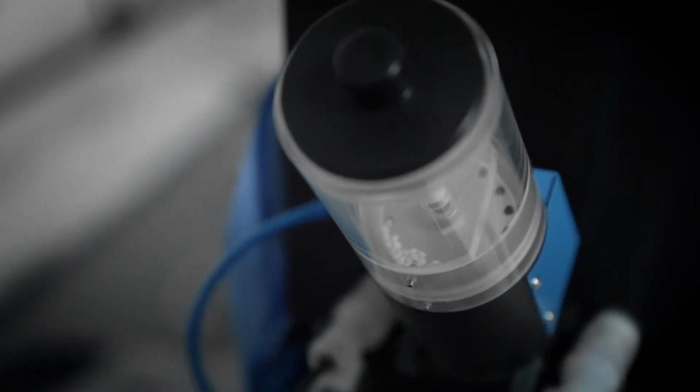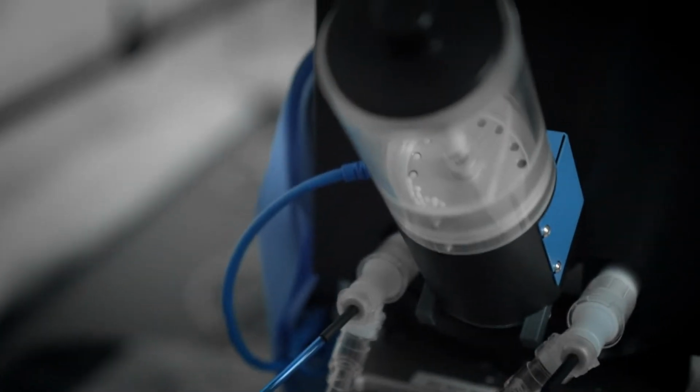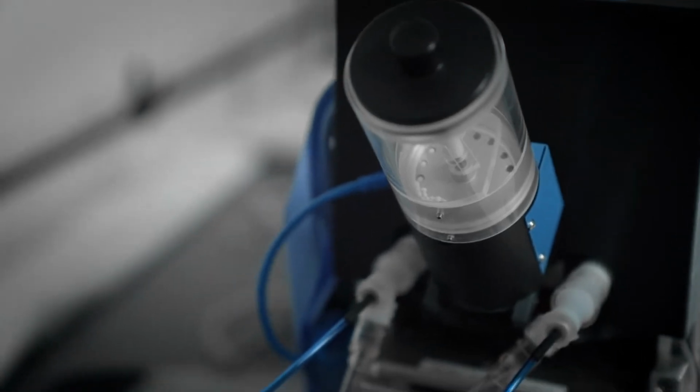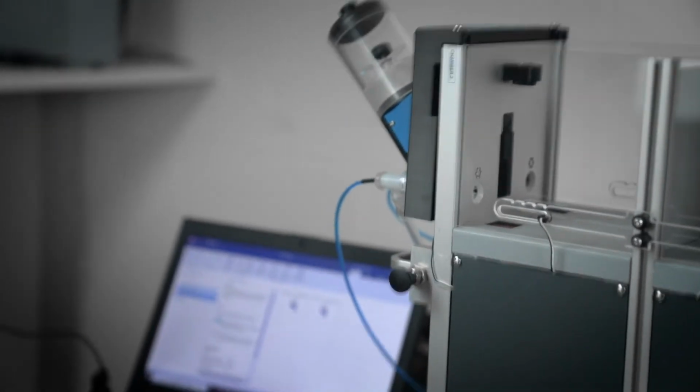So basically, every time that the animal has done what he has to do and the test is accomplished, a pellet will be dispensed. Consider that these pellet dispensers are quite sophisticated because there is a system to check if the pellet has really been dispensed, and if not, the pellet keeps rotating until it really happens. It's not just a motor that relies on the fact that the pellet goes down. There is an internal system that does a check if the pellet has been dispensed or not.